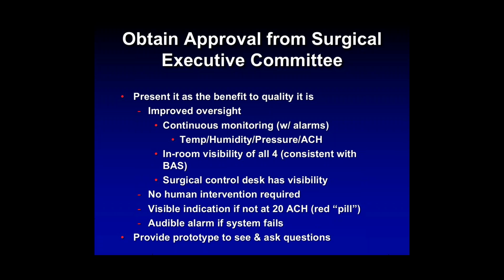And lastly, one of the big deals is that it would not require human intervention. They don't want to have to go throw a switch on the wall to put it into 20 air changes per hour, and they don't want to have to remember to turn it off when they're done. Lastly, we talked about the visible indication that if it's not at 20 air changes per hour, you'll see something red on that user interface to let you know.